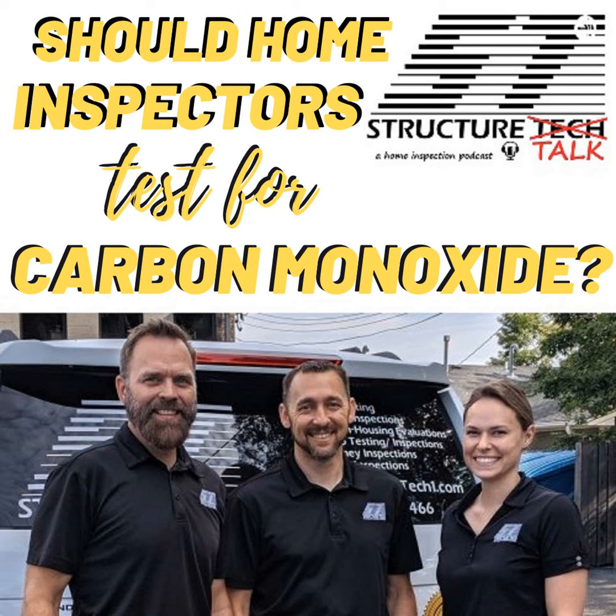Sure. And I know where you're going with this, and I don't know what's so magic about the number 400, but the whole issue with having high CO, number one, if you have any problem with that furnace where the CO leaks out, it leaks out of the furnace, it leaks out of the vent, or you have a failed heat exchanger and it leaks into the airstream, the higher the CO level, the greater your risk to have somebody die in their sleep. The greater risk you have of carbon monoxide poisoning. When the CO is really low, even if it were to backdraft into the house, people probably aren't going to die. So that's one part of it.